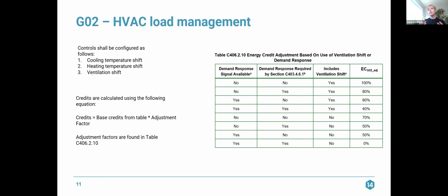So the first column of our adjustment factor table asks: is a demand response signal available from a controlling entity other than the owner? Yes or no. Does your utility have a demand response program that is available? Is demand response required by section C403.4.6.1? We will go through that section. And do your controls include a ventilation shift? So if we are in a location where a demand response signal is available, it is not required, and we do include a ventilation shift, we are going to achieve 80% of the credits available.